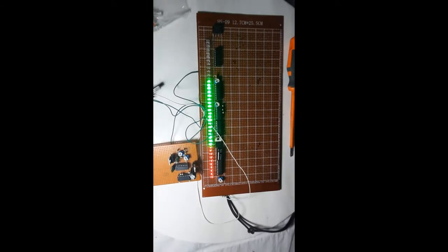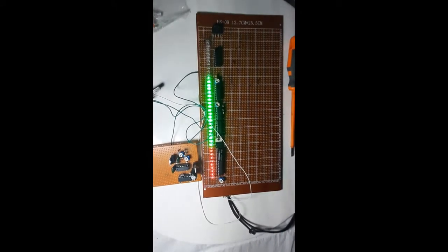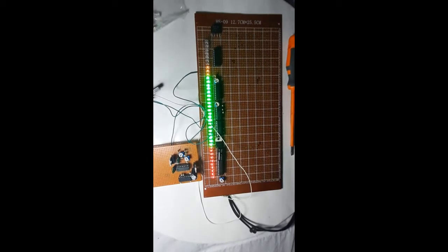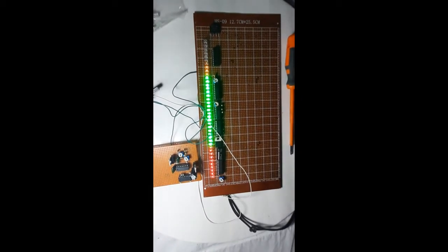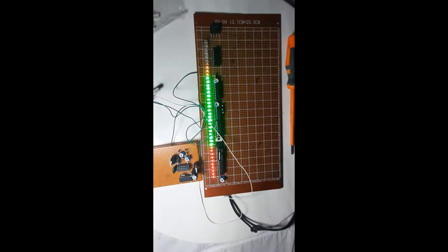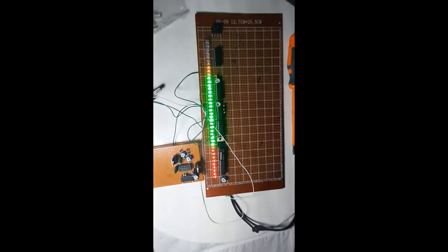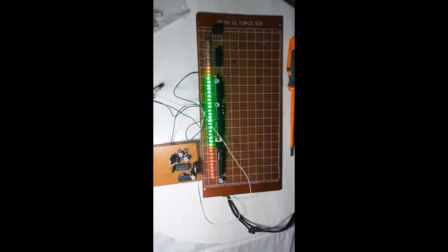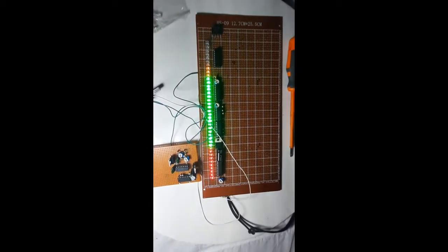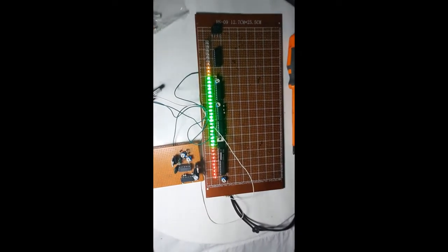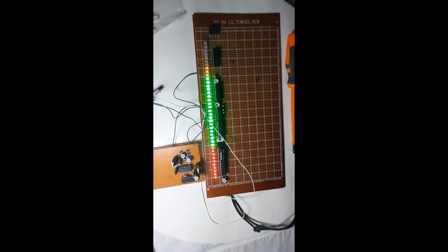So we have learned that there are basically 3 faults, the errors basically. The faults, we call those errors in the system. One is zero error, the other one is the span error, and the third one is the linearization error. This linearization error generally in most cases we cannot correct, but with modern electronics, yes, we can. And the zero error and the span error, anyway we can correct those, right?